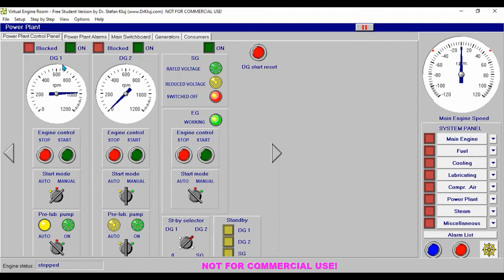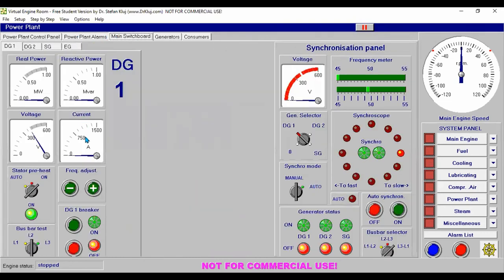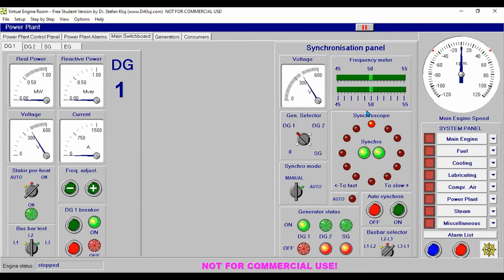We check that there are no problems. Once the RPM is stable, go to synchronization. When we set it to number one, it rotates automatically. Set our synchronization mode to manual. When it reaches 11 o'clock position, that's the time to close the breaker. We can use the frequency adjustment to slow down the rotation. Once it reaches 11 o'clock, the synchronization is achieved.